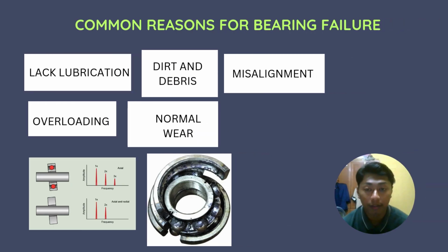So we already know what the signs of bearing problems are. Next is what the common reasons for bearing failure are. So there are 5 common reasons. Firstly is lack of lubrication. Second is overloading. Third is dirt and debris. Fourth is normal wear. And lastly is misalignment.